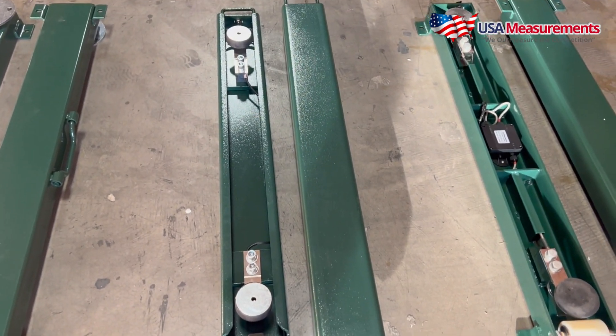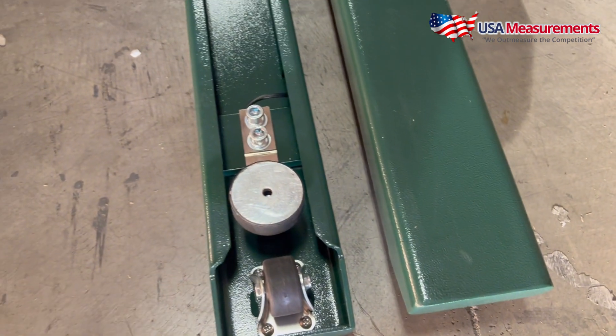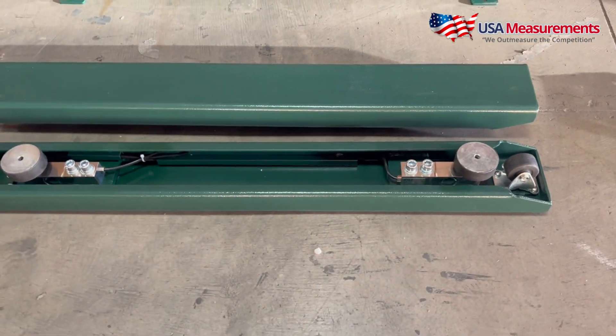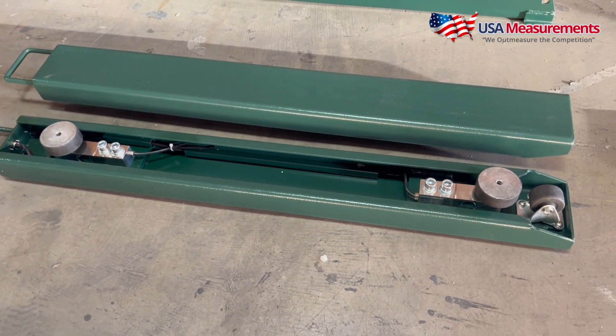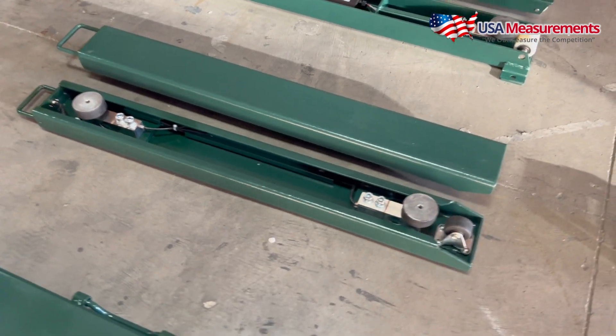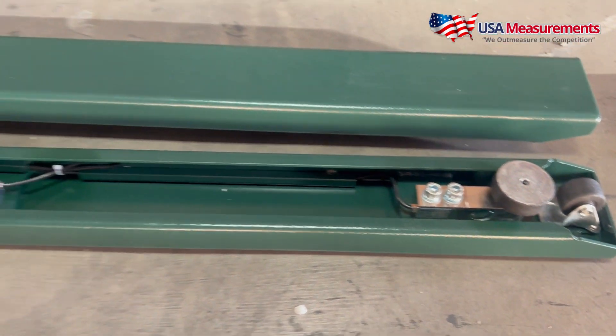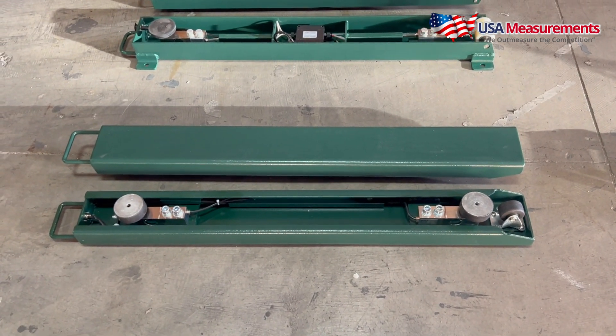The ESB Plus is very similar but with a few differences. We again have the caster wheel, leveling foot, and load cell, but there are no junction boxes, so there are fewer parts involved. Depending on your application, in this instance all you have is four load cells and an indicator — very simple, easy setup. However, you do have exposure to cables in certain areas, so depending on the application this could or could not be the right weigh bar for you.